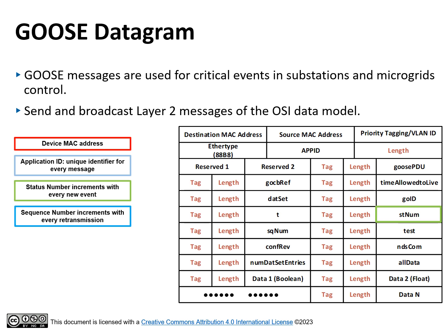A Goose message is an IEEE 802.1Q Virtual Local Area Network ID, VLAN ID, and a unique Ethernet type, 88B8. The application ID, app ID, field is a 2-octet field. The length field represents the length of the overall Goose datagram minus 8 bytes and is followed by 2 reserved fields left out of the standard for future use.